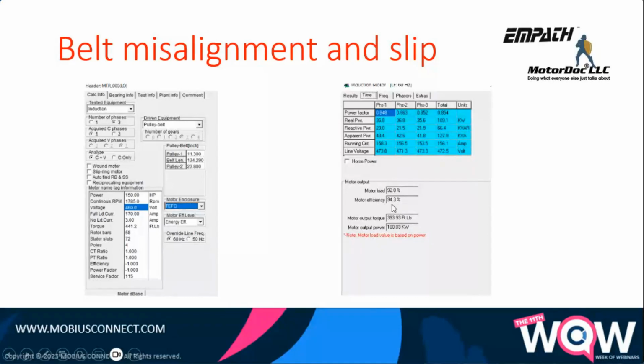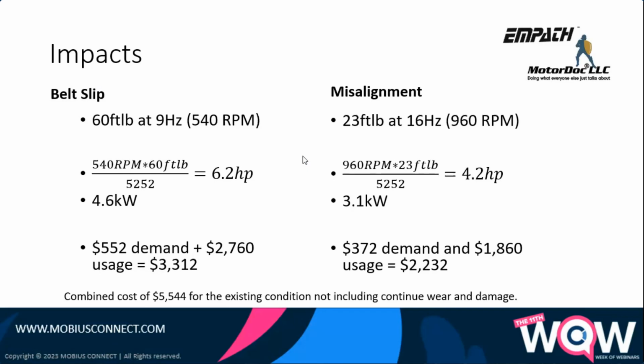So let's take a look. We have 11.5% belt slip, so the belt's worn, and a little bit of tension. So belt slip comes out to 4.6 kilowatts, or 552 demand, usage 3,312. The misalignment at 23 foot-pounds at 16 hertz, using those other formulas, comes out to $2,232 total, or $5,500 just by fixing the belts and belt alignment.